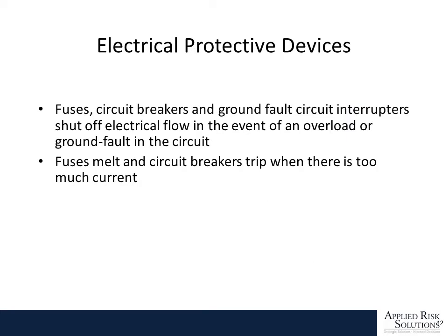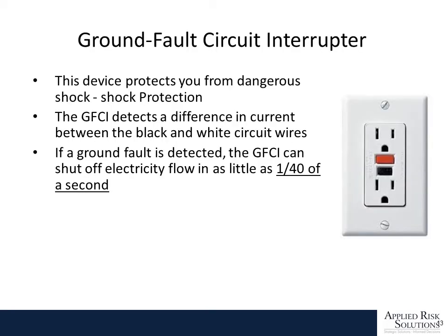There are a lot of electrical protective devices engineered into our systems to help prevent us from being shocked and for preventing fires. Fuses, circuit breakers, and ground fault circuit interrupters all shut off the electrical flow in the event of an overload or a ground fault in the circuit. While fuses melt and circuit breakers trip when there's too much current, the GFCI, ground fault circuit interrupter, will trip if it senses a difference in the current leaving the outlet and the current coming back.